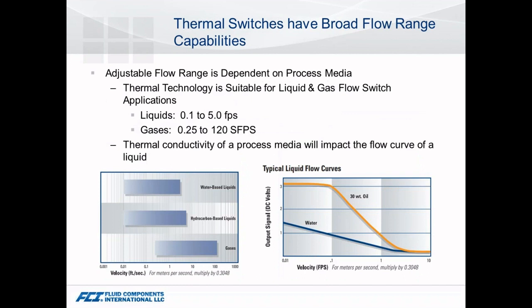Where things kind of started on the thermal switch side, we're really looking at liquid and gas type applications. True benefits include very low flow capability — in that 0.1 to 5 feet per second for liquids, and gas has a much broader range. When you look at liquids, the range is going to vary — water-based versus hydrocarbon shows a slight difference in range, really related to the cooling effect of the liquid itself, and you can see it's quite lower than that of gases.